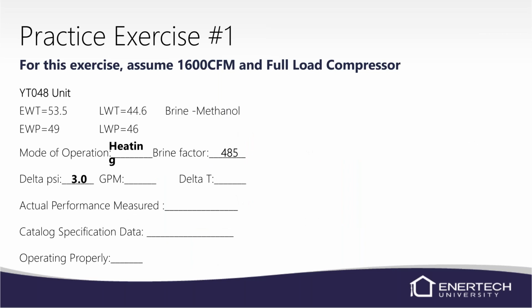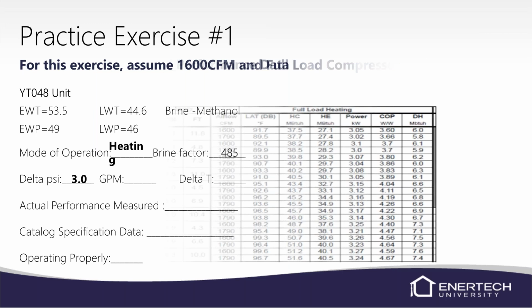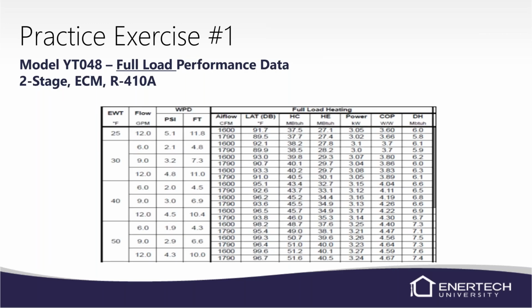Again, we're in heating mode, brine factor of 485. We have a 3-pound pressure drop at our 50-degree entering water temperature. So this is where we're going to pull up the manual. We're going to go to, obviously, the correct tonnage unit. We'll come down to the 50-degree entering water. We are really at 52, but 50 is close enough for what we're trying to get into. We had a 3-pound pressure drop. So 2.9, that's pretty close. I mean, a 0.1, I'm not really too worried about that.